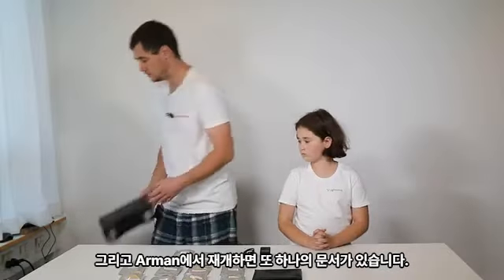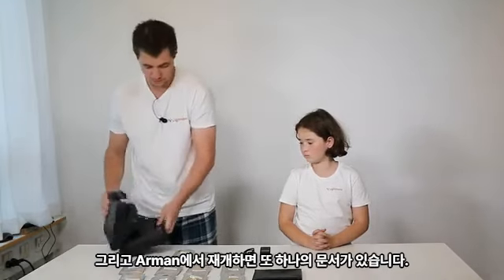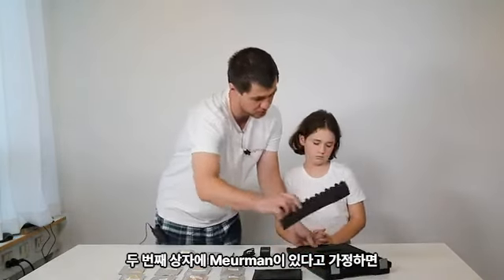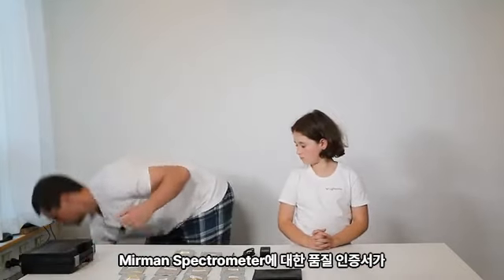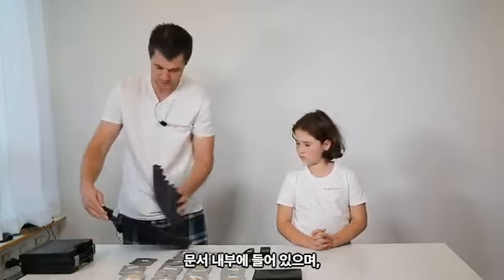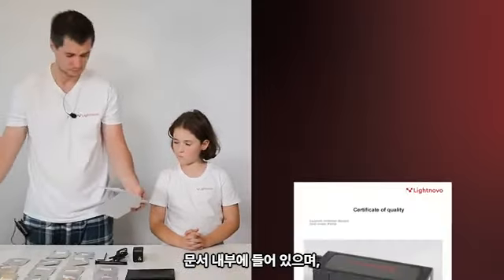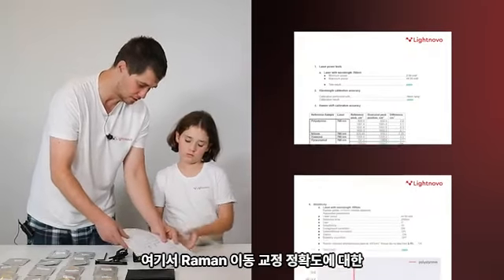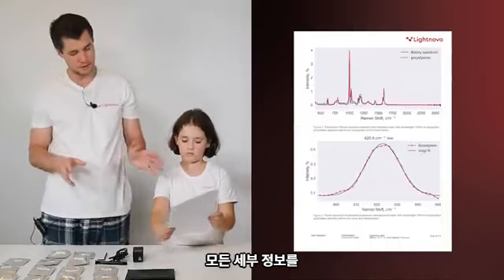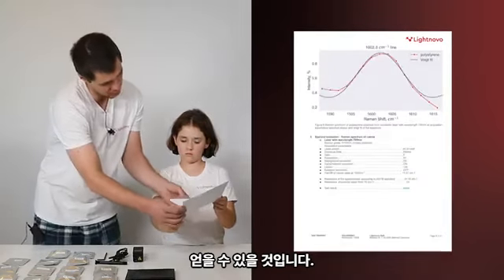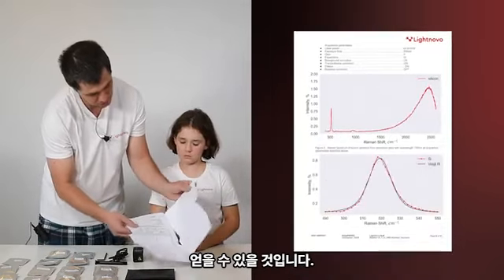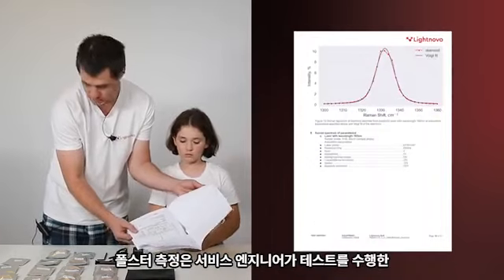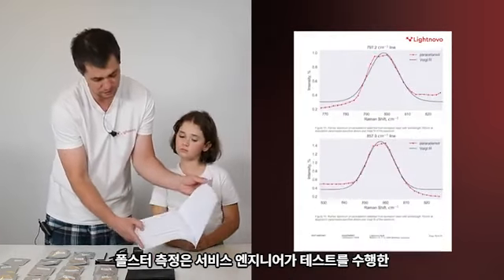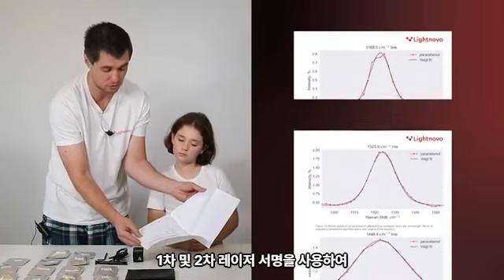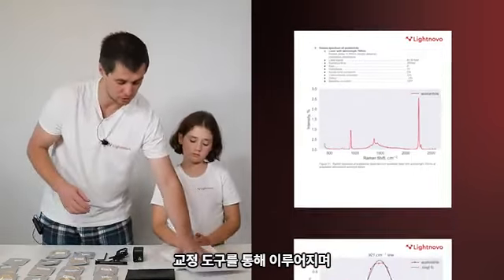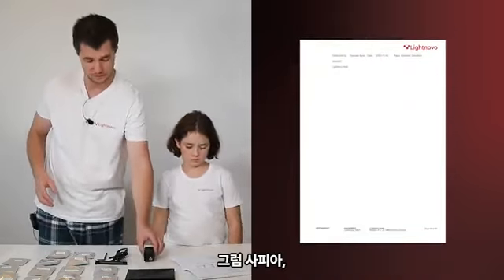Very nice. And by the way, we also have one more document. If you receive mini-Raman, oh, not in this box, in the second one. If you receive mini-Raman, you will get inside the document, certificate of quality for mini-Raman spectrometer, where you will get all details of Raman shift calibration accuracy, polystyrene measured with our calibration tool with first laser, with the second laser, signature of the service engineer who did the testing. And this document you can use every time you are unsure with the mini-Raman performance.